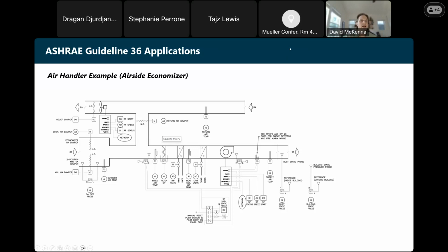And this schematic, I think, really helps to show how we can save energy. So in this case, again, we're looking at an air side economizer. With this sort of setup, we can look at things like outside air temperature, and the control sequence might read something like, okay, when the enthalpy of the outside air is lower than the enthalpy of the return air, as indicated by this temperature sensor, then we can close this damper, the return air damper, and basically flush nothing but clean outside air through your building because it's free cold air. So in that case, you won't have to run your chilled water coil, which means that you can turn your compressor off back at your chiller, which is the main energy hog of the system. So it's basically free cooling, and it's essentially a mechanical equivalent to opening a window instead of running your AC.